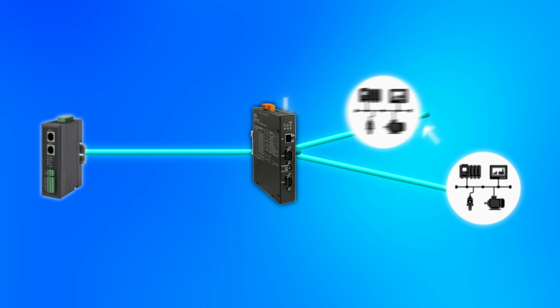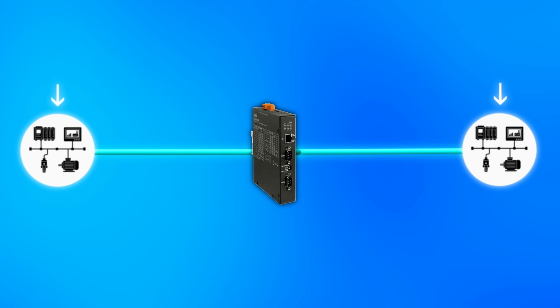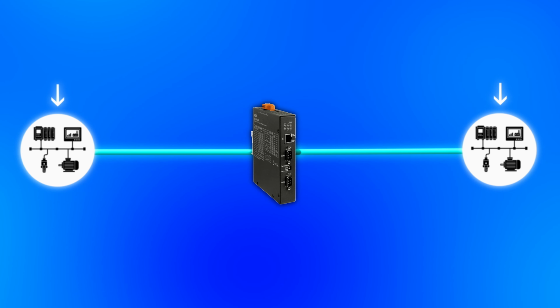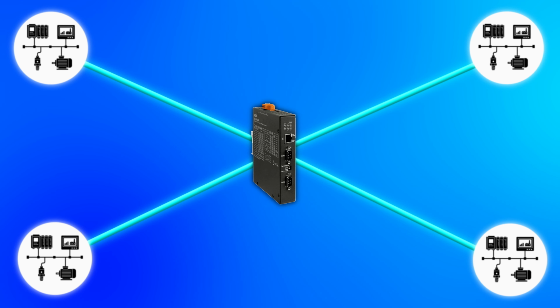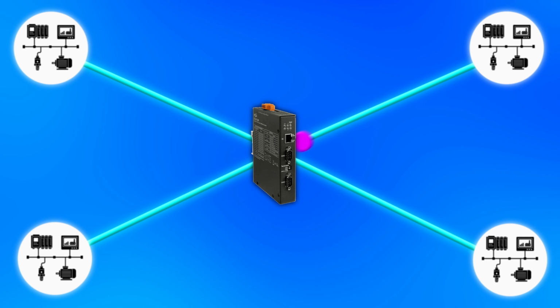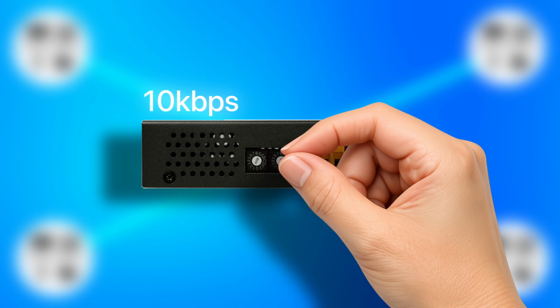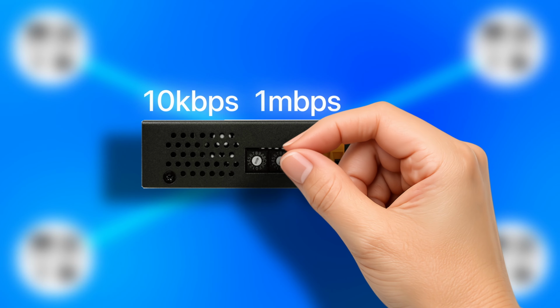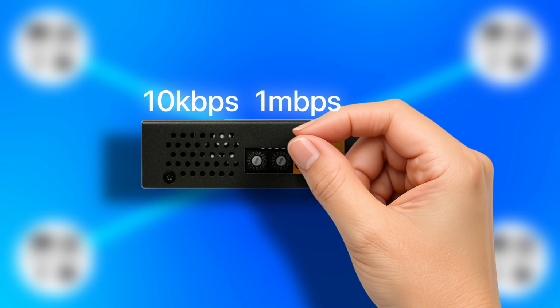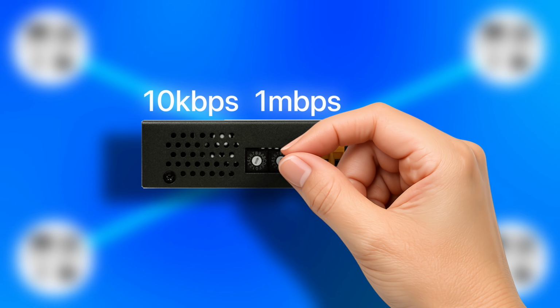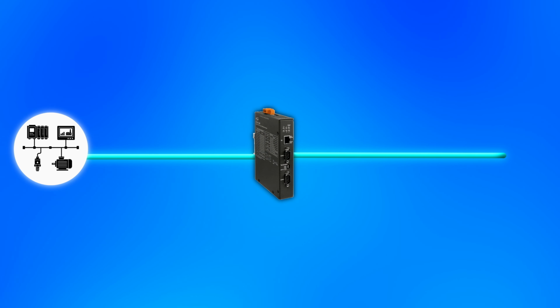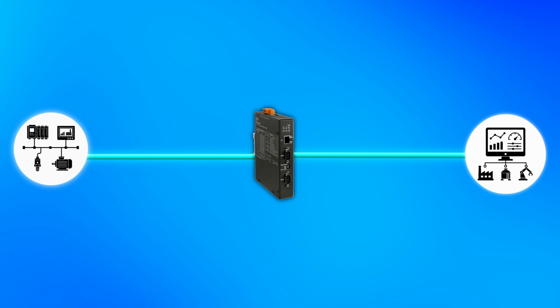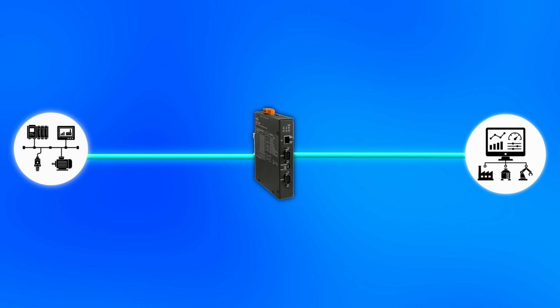But what makes it stand out is that it goes beyond a simple gateway. It can function as a CAN bridge connecting 2 separate CAN networks together through the Ethernet infrastructure, and it can act as a CAN message router, allowing up to 4 different CAN networks to communicate with each other simultaneously. The baud rate on each CAN port is adjustable from 10 kilobits per second up to 1 megabit per second via rotary switch, which means that no software configuration is needed just to set up the speed. For any installation where CAN data needs to reach an Ethernet-based monitoring system, historian, or SCADA platform, the ECAN 240 is what makes that connection clean and reliable.